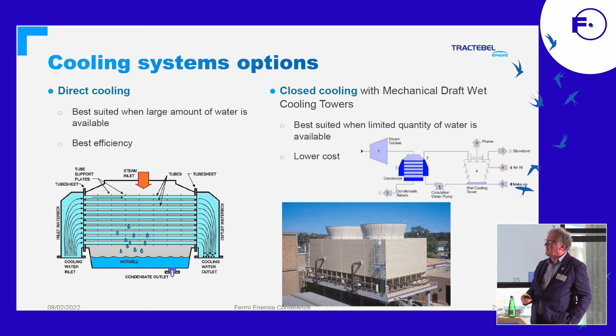This is an example for the Kunda site. The layout is absolutely conceptual; the plant could be moved up a little bit. But it shows that in a direct cooling configuration, we need very long lines, large piping, going out to the sea to reach sufficient depth for water intake, and then returning the water to the bay. So it's quite expensive from the capex point of view.